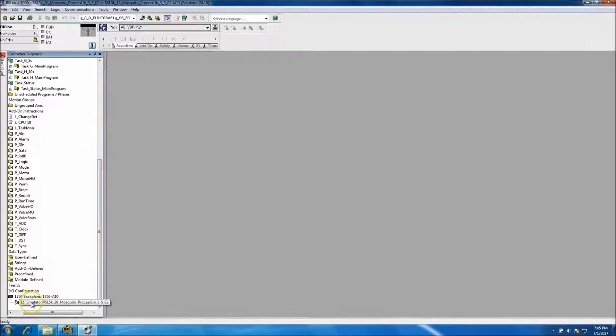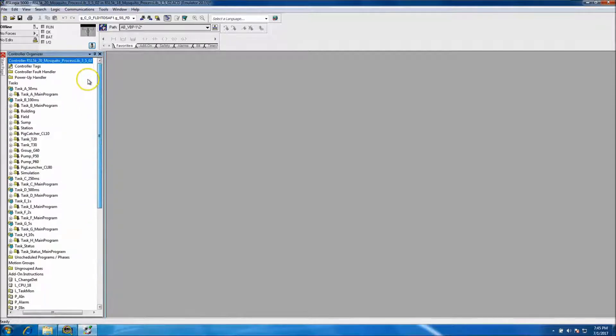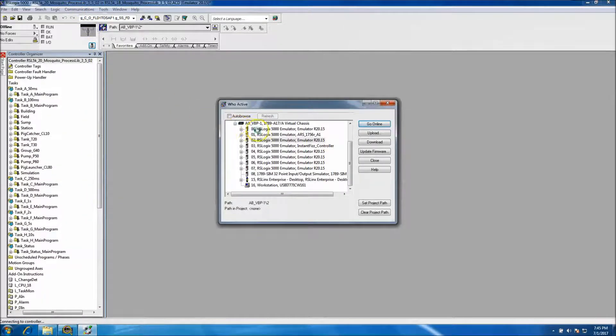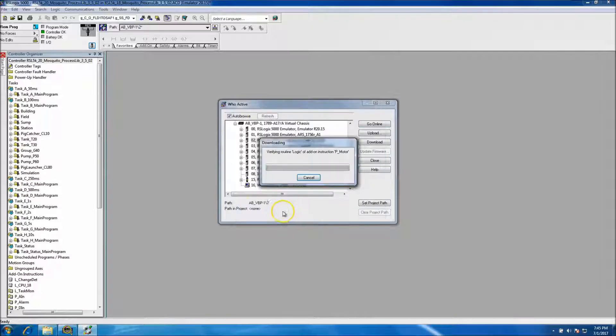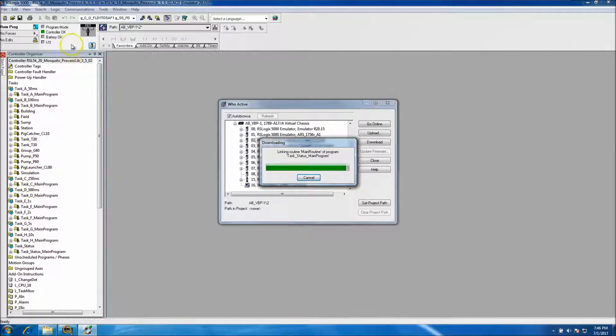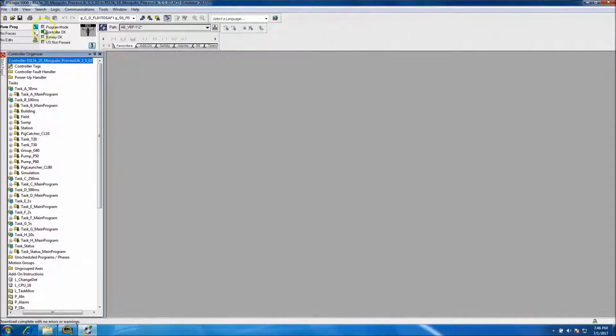I'll go ahead and change the name to 20. I want to make sure that my processor is down here in slot 2. I'll go ahead and go online and download to slot 2. As this is downloading - I didn't have version 18, so it prompted me to change it already; I didn't have to manually select the controller type, it asked me what processor I'd like to use. Then we'll throw it in run mode, and that takes care of the PLC end.